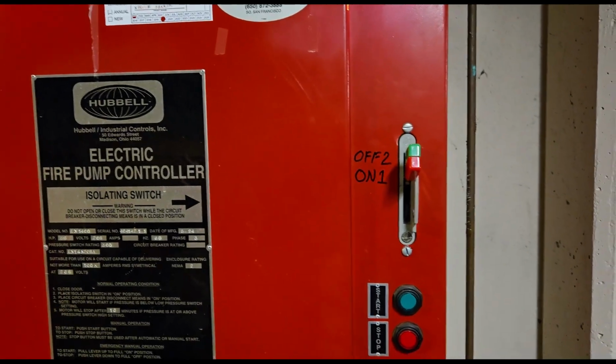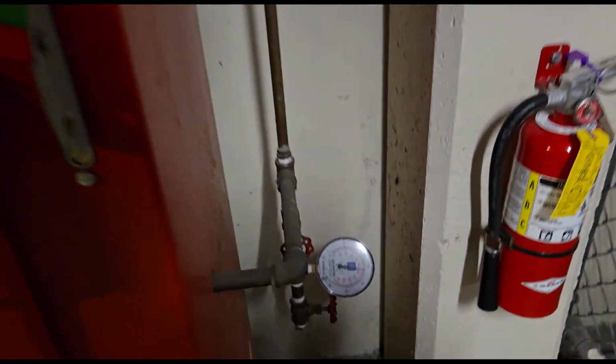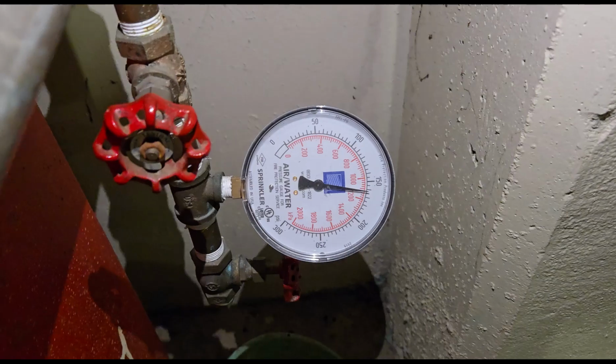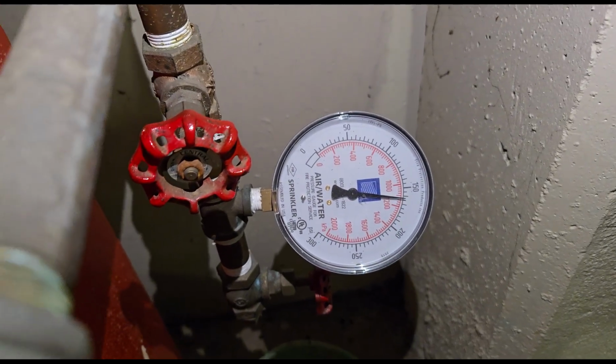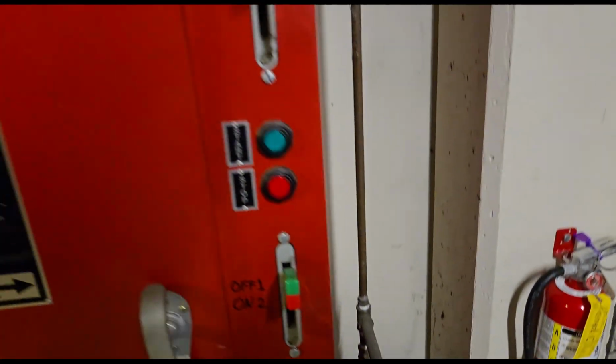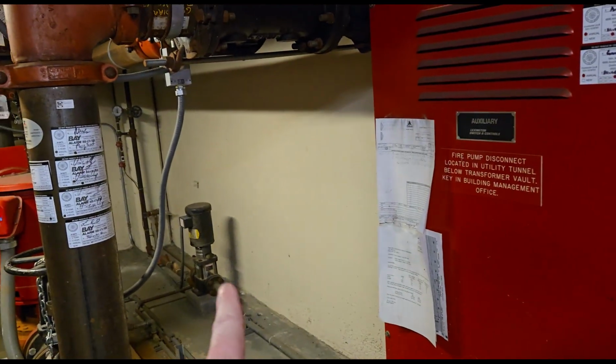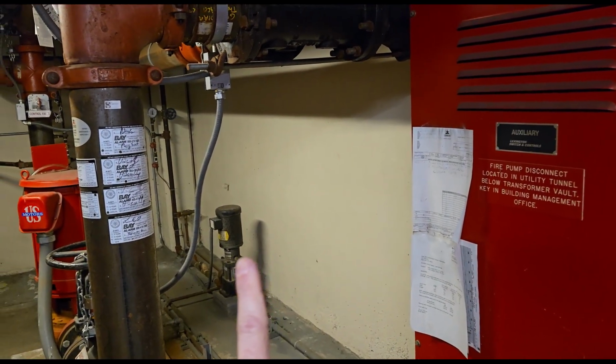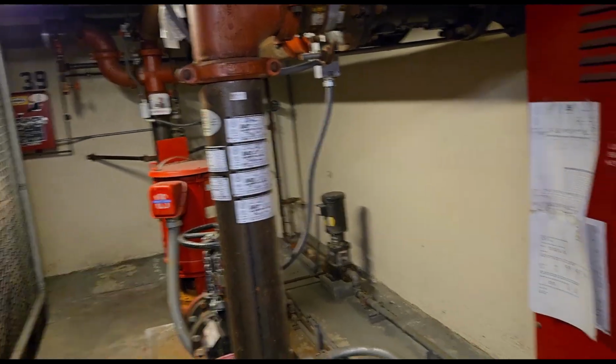And after we do our flow testing, we're going to come back down here. We're going to make sure the pump is back at 150. There we go, we're going to make sure it's back, or 160. And then once it's back on, that means that this little jockey pump is no longer on, it means it's already filled the system. And this one's not on because the power's off.